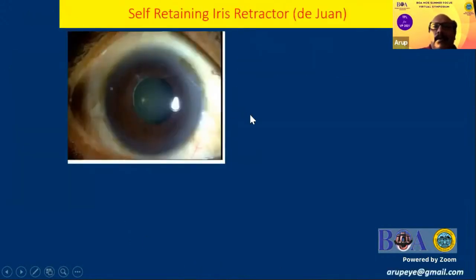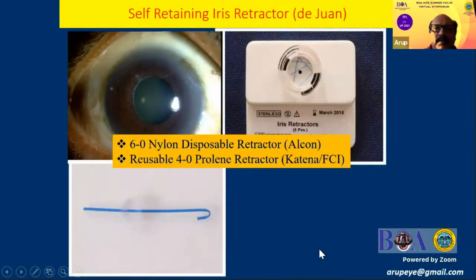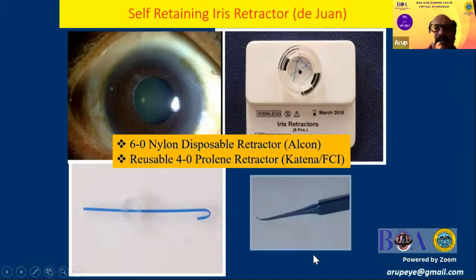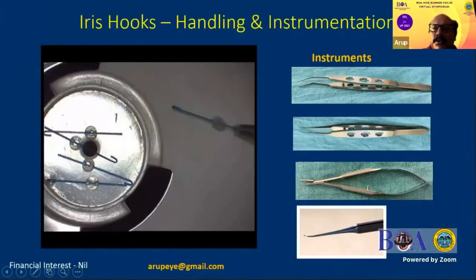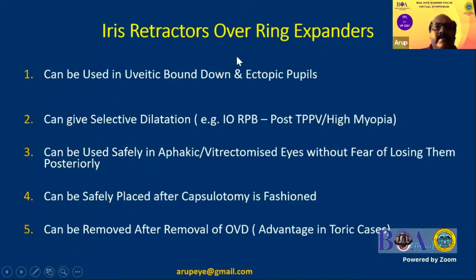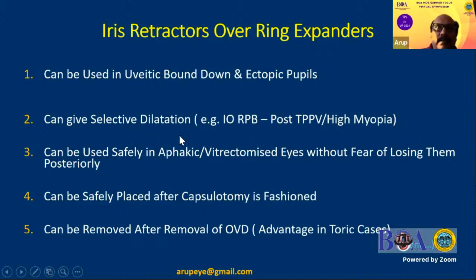Among all the devices, I am a big fan of iris hooks for various reasons. These are disposable devices, very simple to use — you just need a 27-gauge needle to manipulate them into the eye. Why do I prefer iris retractors over ring expanders? You can use them even in uveitic patients with posterior synechiae where the pupil has become ectopic. They allow selective dilation — for example, during vitrectomy with reverse pupillary block or lens-iris diaphragm retropulsion syndrome, I can gently lift the iris from the anterior lens capsule to prevent shallowing of the anterior chamber.